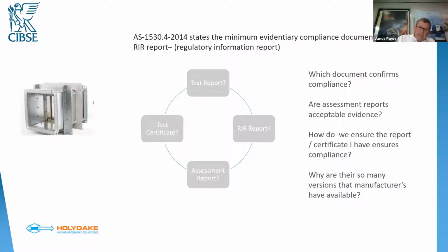And then after that, what we'll tend to do is a number of section 10 tests. So we want to make sure that the fire damper performance will be the same in a gyprock wall, for example, or a speed panel wall, or recently we tested one in a wooden floor, actually, for that matter. And we want to make sure that the perimeter seal will stay intact and that the fire damper won't radiate too much heat through its case or cause any other problems. So we'll run through a series of those tests, and they all have different values and slightly different requirements. So we might have 8 or 9 different test reports for a particular fire damper.